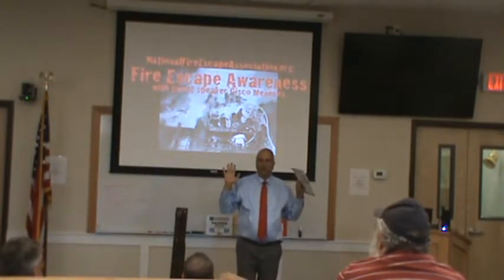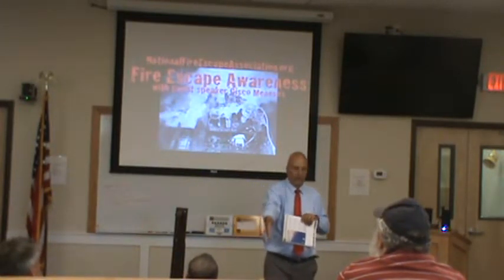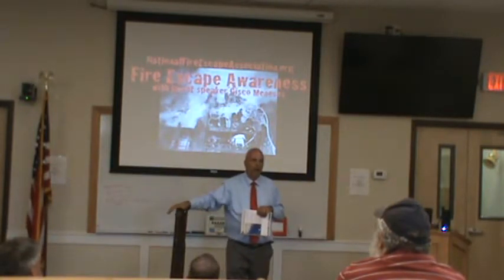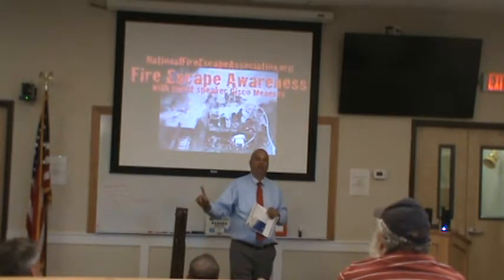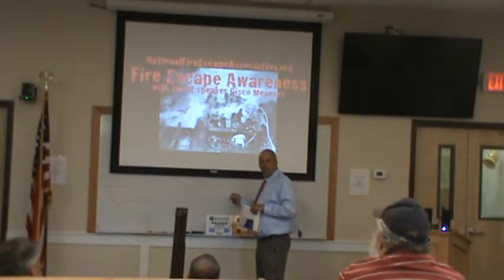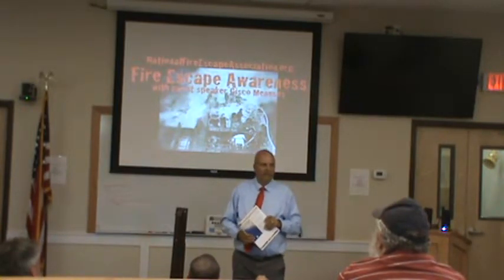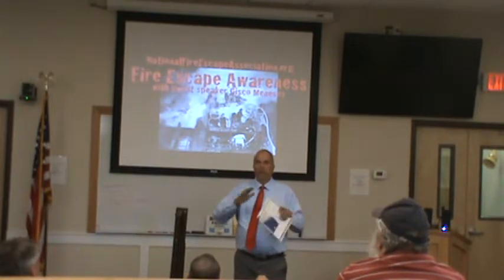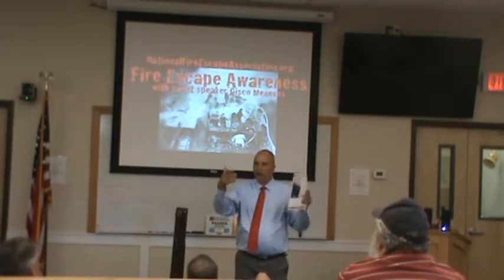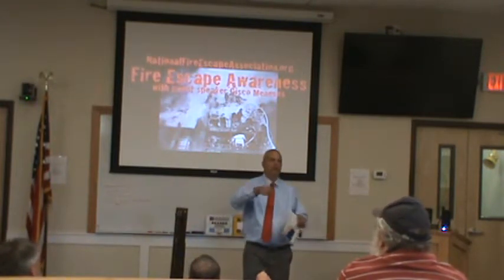Have your design professional, or others acceptable to the building official, submit a deficiency report to the city official. From there, they'll determine whether this is going to fall under routine maintenance or it's going to require a permit. A lot of times what triggers a permit is as soon as I penetrate the wall. That's one of the big pieces, especially down in Philadelphia. You can do anything you want to a fire escape, it's routine maintenance, as soon as you penetrate the wall, they want stamped design drawings, and that means there's an investigation inside, because that triggers a permit.